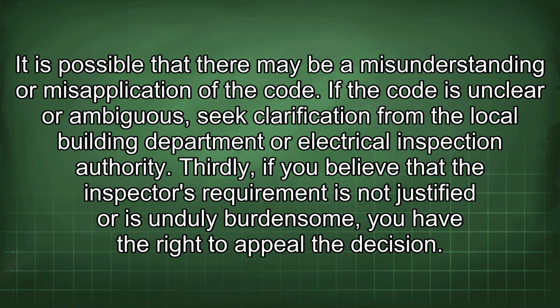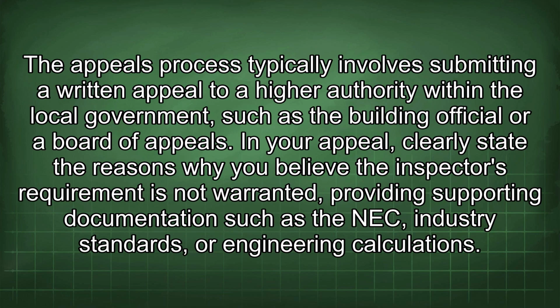Thirdly, if you believe that the inspector's requirement is not justified or is unduly burdensome, you have the right to appeal the decision. The appeals process typically involves submitting a written appeal to a higher authority within the local government, such as the building official or a board of appeals. In your appeal, clearly state the reasons why you believe the inspector's requirement is not warranted, providing supporting documentation such as the NEC, industry standards, or engineering calculations.